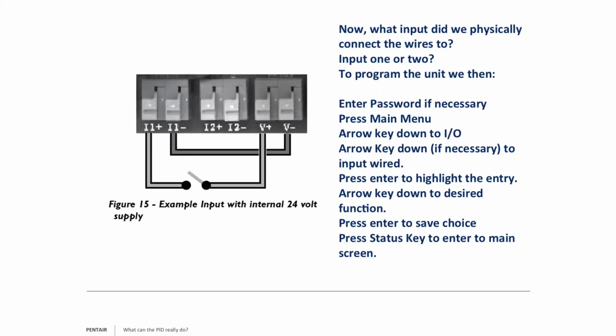Now, we're looking at how to program this, because the first thing we always have to do is, of course, wire it. So here's our wiring diagram. We did our wiring, but remember, that's only half the steps you have to do. Now we have to make sure we properly program our Pentek Intellidrive to do what we want. In this case, say we want it to be a float switch, whatever, we're going to have to enter in the password if necessary.